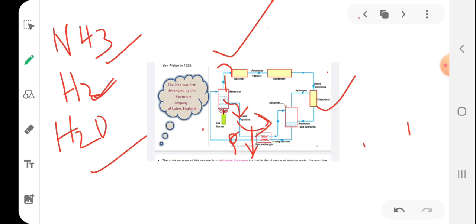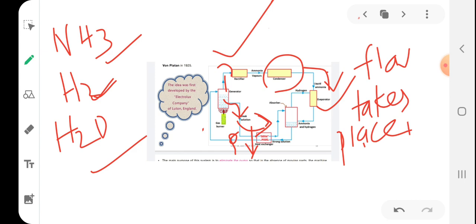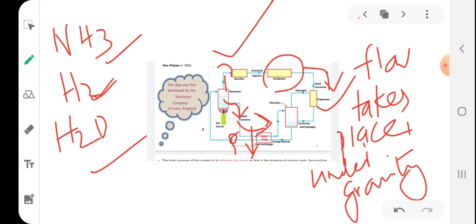Okay. What happens to the ammonia vapors in the condenser? They are condensed using some external cooling source, or by directly rejecting heat to the atmosphere, and they become liquid. The liquid ammonia flows to the evaporator. This flow takes place under gravity. That is why there is no usage of a pump or compressor. It takes place merely due to the effect of gravity. So it flows under gravity to the evaporator, where it meets the hydrogen gas.